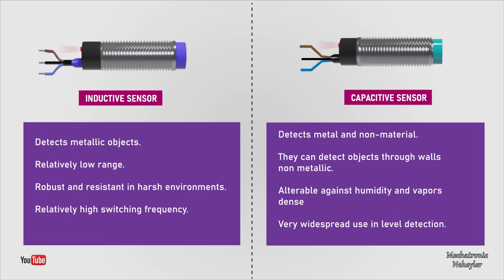Inductive sensors detect only metallic objects, with a relatively low range that varies depending on the nature of the alloy. They are robust and resistant in hostile environments, unalterable against shocks, vibrations, and dust, and have a relatively high switching frequency, making it possible to control the passage of parts at high speed. They have no moving parts subject to wear. Capacitive sensors detect ferrous metals and any other type of material, and can detect objects through non-metallic walls. They are alterable against humidity and dense vapors. They have widespread use for level sensing — for example, through plastic bottles — and for short-range sensing of transparent materials. They have an absence of mechanical wear and long useful life.